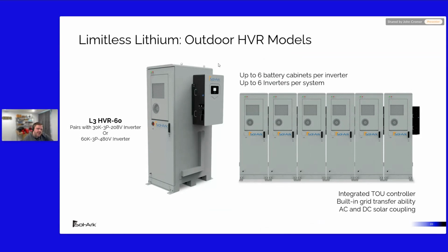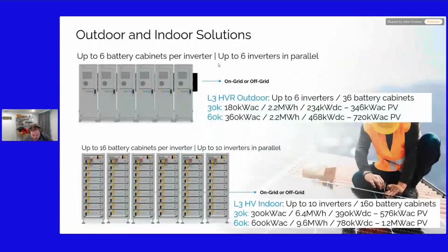The outdoor version, you could have up to 6 battery cabinets and 6 inverters per system. You can do much larger systems with the indoor series. With the indoor, you can go up to 10 inverters and up to 16 battery cabinets per inverter. So with the indoor series, you can do a 600 kilowatt, almost 10 megawatt hour ESS system. Whereas we constrain the outdoor series design to 6 inverters and 6 battery cabinets per inverter, up to a total of 36 battery cabinets.